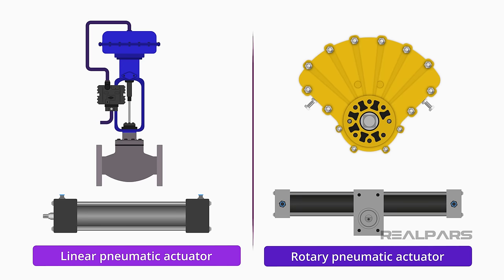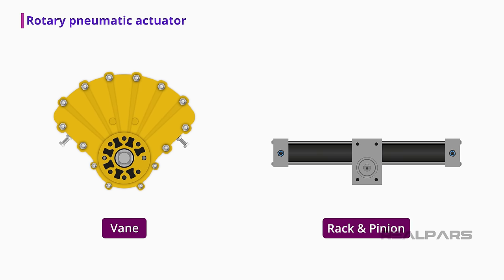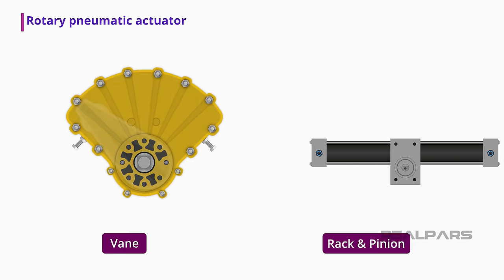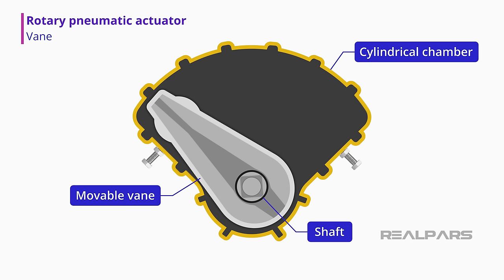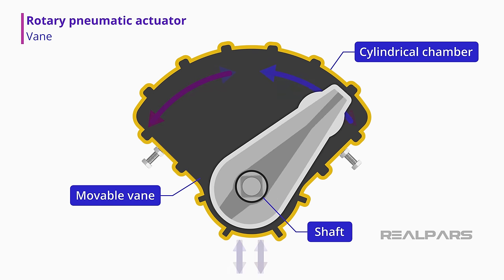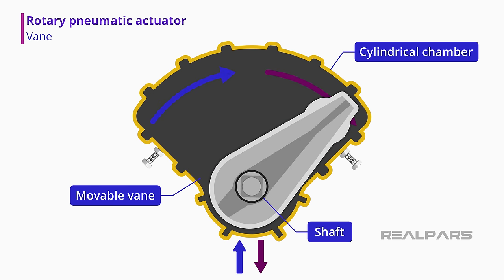Let's look at some examples of how rotary and linear pneumatic actuators are operated, as there are many different types of each. In the rotary pneumatic actuator category, the vane style and the rack and pinion style are very common. Vane actuators have a cylindrical chamber in which a movable vane is mounted on a shaft. Pneumatic air under pressure applied on one side of the vane causes it to rotate through its stroke.